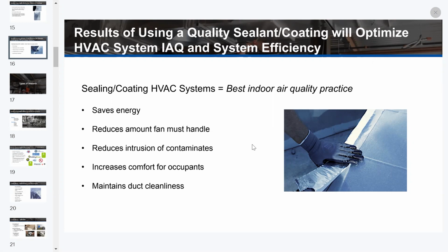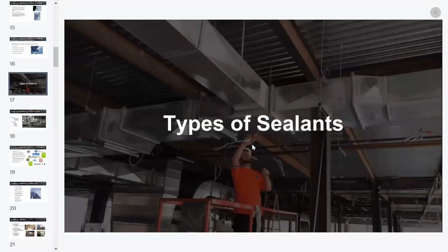And keep in mind that mastics must have microbial inhibiting properties and long-term performance. The goal is to seal that system, preferably for the life of that system, and making sure that whatever you seal that system with is not going to add to any particular growth if there's any debris or water that gets into that system. The sealant product itself should never become a food source for microbial growth. And that's just one of the key things.